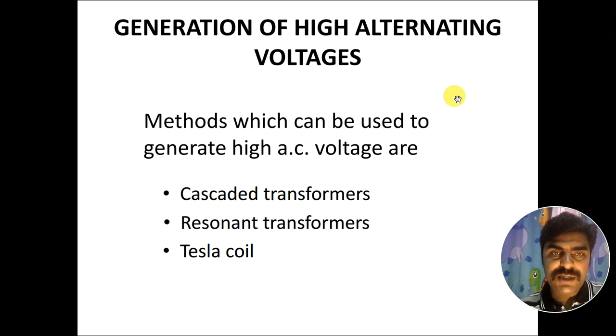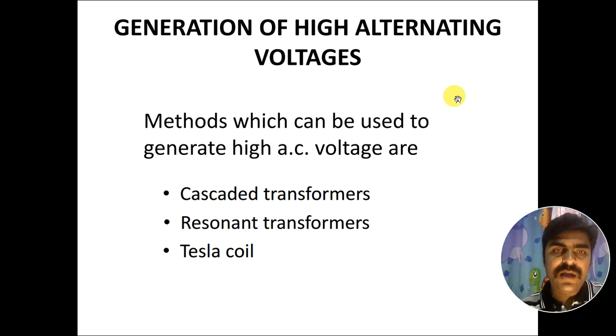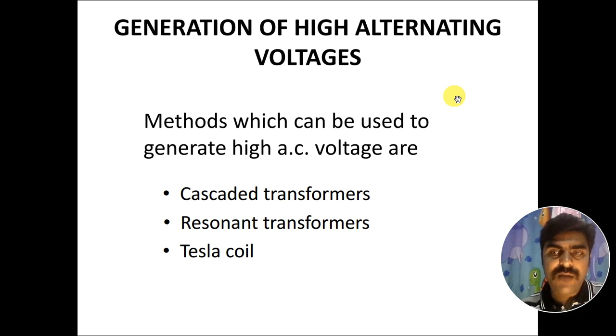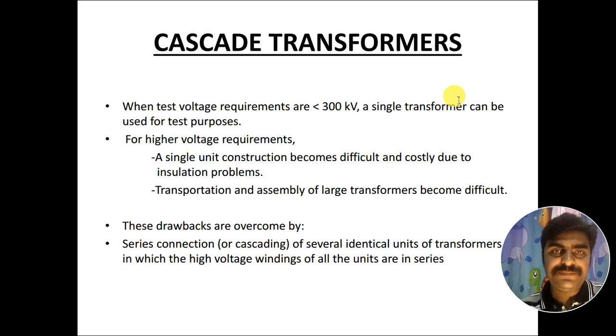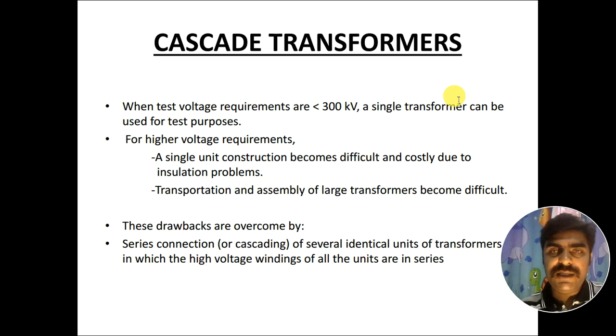There are three methods used to generate high AC voltage: cascaded transformers, resonant transformers, and Tesla coil. In this video I will discuss about the cascaded transformers, and in the upcoming two videos I will discuss about the resonant transformers and Tesla coil. When test voltage requirements are less than 300 kV, a single transformer can be used for testing purposes — meaning a single transformer can generate up to 300 kV.